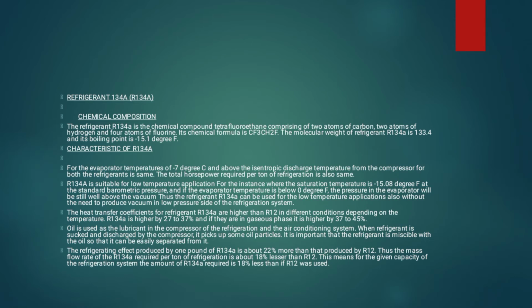The molecular weight of R134A is 102, and its boiling point is negative 15 degrees Fahrenheit. Okay? So, mapapansin natin na ang CF3CH2F or R134A is a little heavier than the R12. For the evaporator temperature, negative 7 degrees, the isentropic discharge temperature from the compressor for both refrigerants is the same. The total horsepower required per ton is also the same.